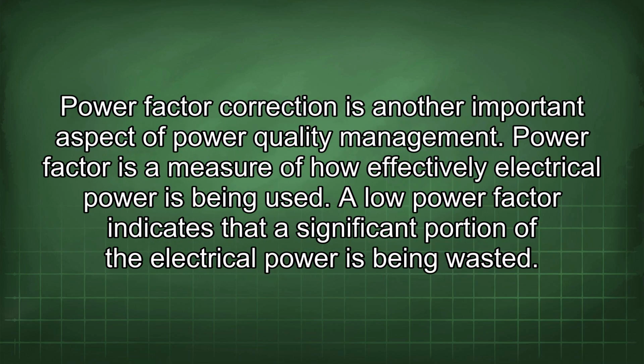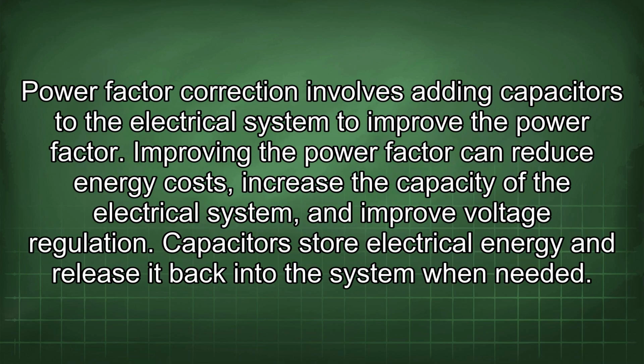Power factor correction is another important aspect of power quality management. Power factor is a measure of how effectively electrical power is being used. A low power factor indicates that a significant portion of the electrical power is being wasted. Power factor correction involves adding capacitors to the electrical system to improve the power factor. Improving the power factor can reduce energy costs, increase the capacity of the electrical system, and improve voltage regulation.